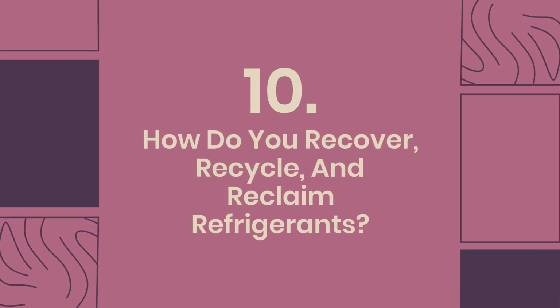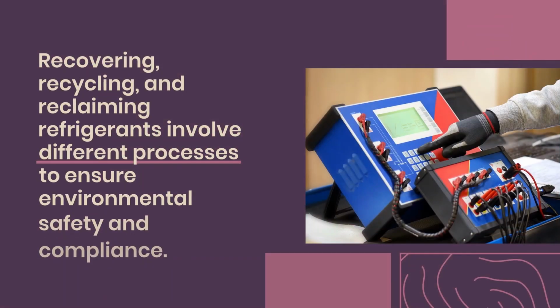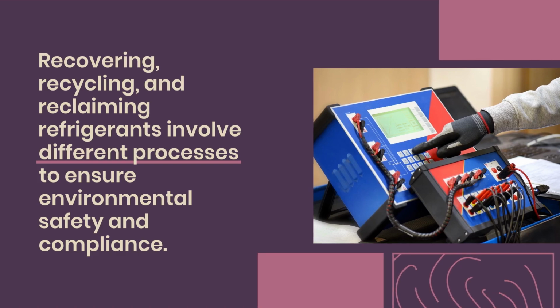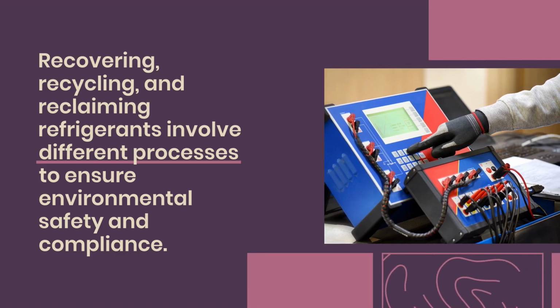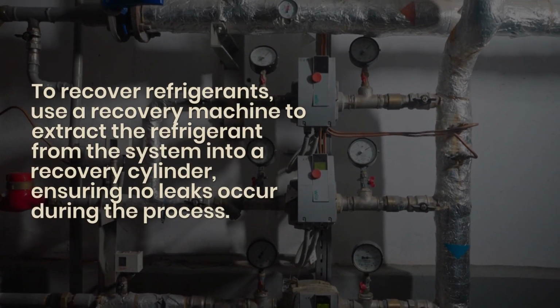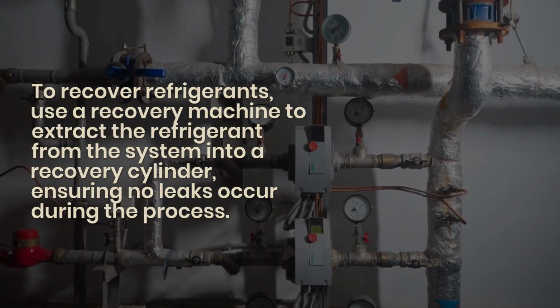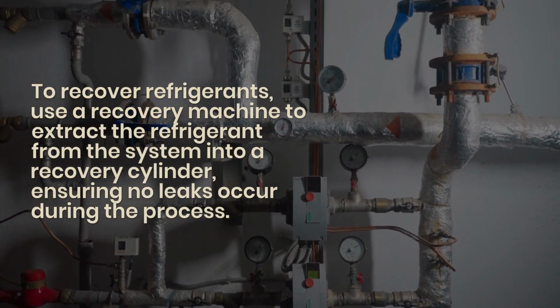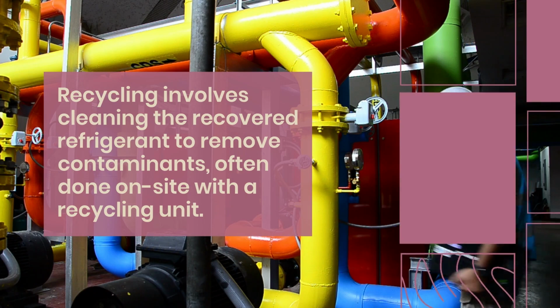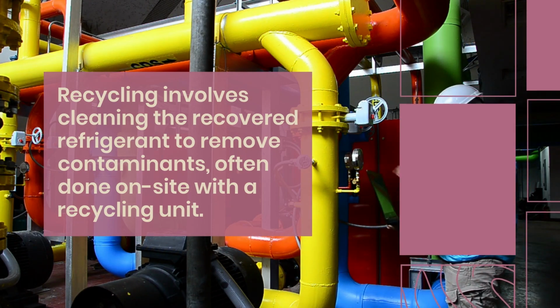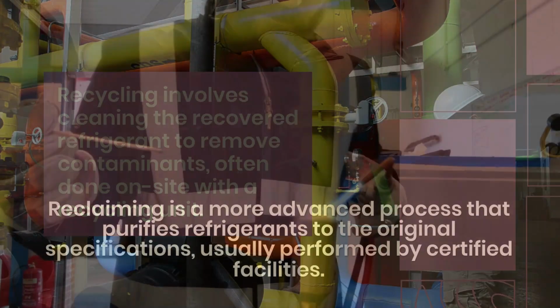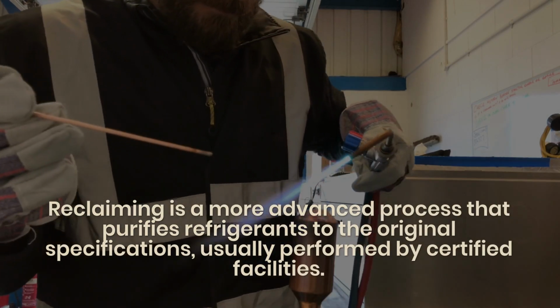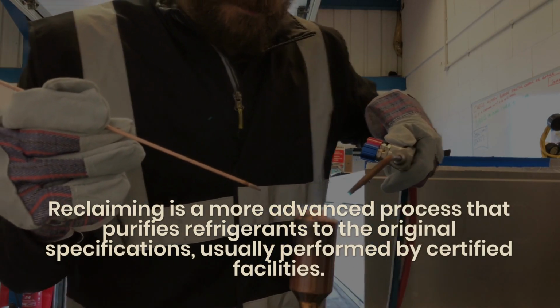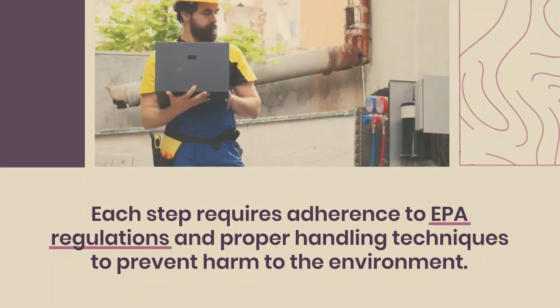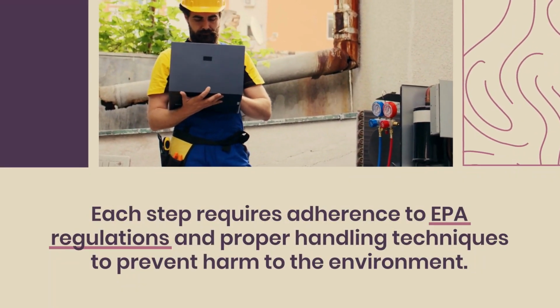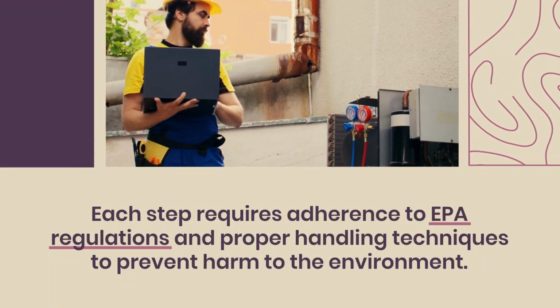10. How do you recover, recycle, and reclaim refrigerants? Recovering, recycling, and reclaiming refrigerants involve different processes to ensure environmental safety and compliance. To recover refrigerants, use a recovery machine to extract the refrigerant from the system into a recovery cylinder, ensuring no leaks occur during the process. Recycling involves cleaning the recovered refrigerant to remove contaminants, often done on-site with a recycling unit. Reclaiming is a more advanced process that purifies refrigerants to the original specifications, usually performed by certified facilities. Each step requires adherence to EPA regulations and proper handling techniques to prevent harm to the environment.